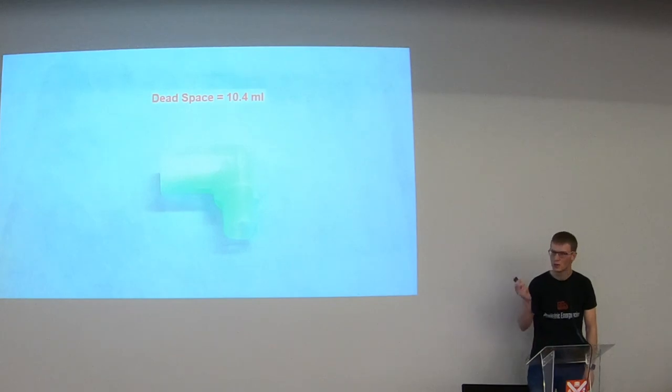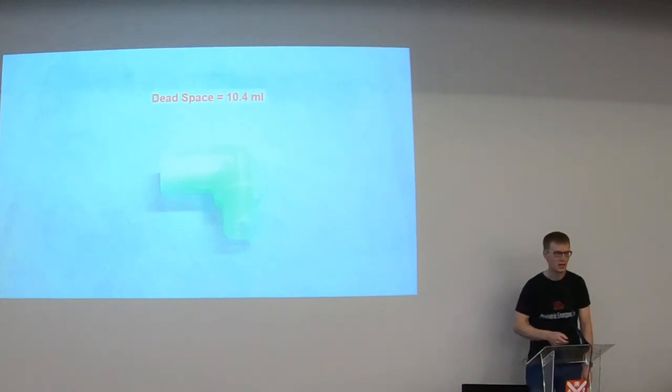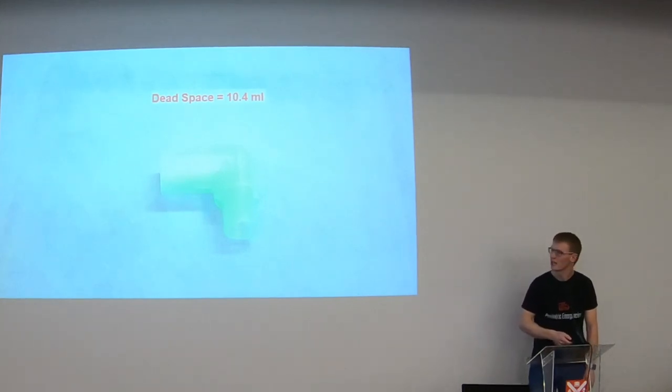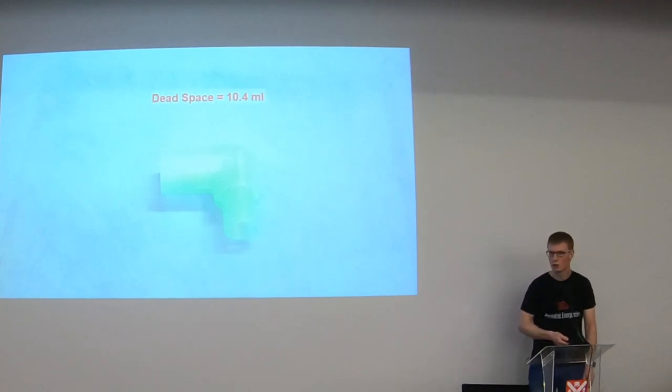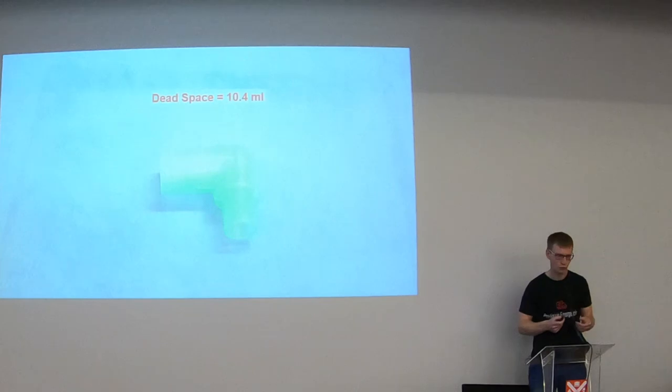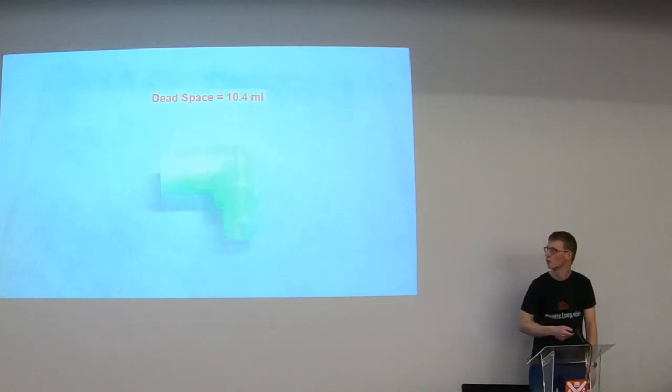This one surprised me when I was looking at the values of dead space. The angle piece, 10.4 mils is a whopping amount. We don't use them in the unit at all. We put our tubing directly onto the end of the endotracheal tube to try and avoid issues with dead space.